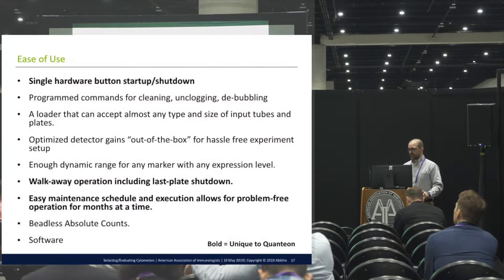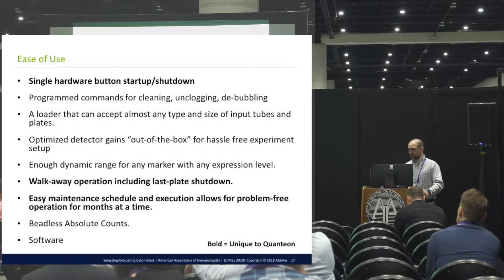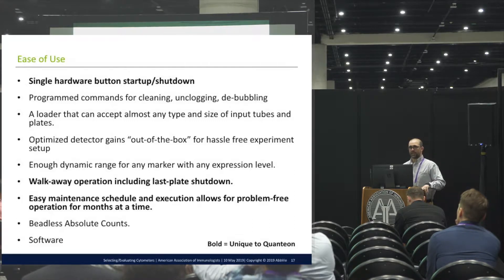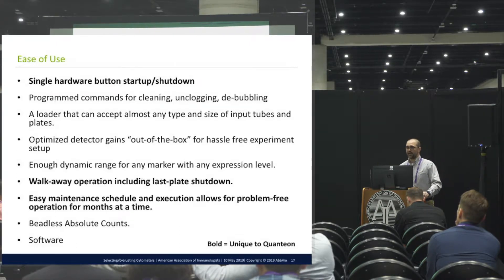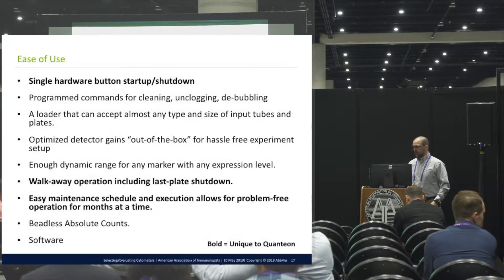Of course it has programmed commands for cleaning, unclogging, and debubbling. You don't need to put any additional tubes or plates on it because it has cleaning solutions on board that can run through and unclog and clean the instrument for you. The loader has the capacity to accommodate pretty much everything you'd want — any kind of plate including UV, flat bottom, 96-well, 384-well, deep-well plates, and a rack of tubes. So whatever user comes into the lab with samples, whether in little bullet tubes or standard plates, you can put them directly on the instrument without transferring to a different format. We've also talked about the optimized detector gains out of the box, easy setup, and the dynamic range.